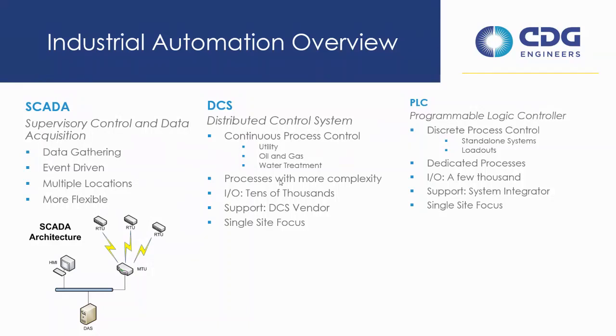DCS and PLCs, like I said, are process control. You'll see DCS systems in a more continuous process control, whereas PLCs are discrete, meaning standalone type systems, whereas a DCS system is a much more complex process. So producing power - you're going to need something that controls the steam generation, the boiler operations, the turbine controls, ash handling. It's got a lot of different pieces, a lot of different information going to one central location, and multiple control systems throughout the entire facility.